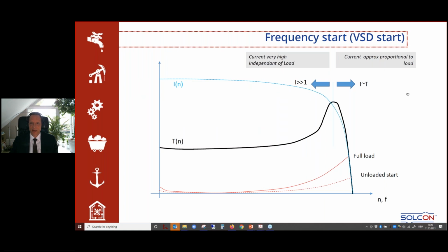Coming to frequency start and IGBT starting. What you see here is a torque speed curve of an asynchronous motor. That's the black curve. Here you see the current curve. Here you see the highest point of torque. It's called breakdown torque. Here you see the load curve at full load or reduced load. And this is against speed or frequency. On the left side of the breakdown torque, the current is much higher than nominal current. And here on this side, you see that the current is approximately proportional to the torque which is needed. So here the current is approximately proportional to the load, and here the current is independent of the load.